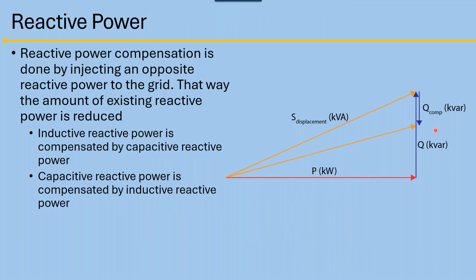Are there harmonics in kVAR? Does the capacitor or reactor have harmonics in it? The answer is no. What we got in the chat is yes, and that's wrong, because there are none. So that's why I call this displacement kVA, because right here there are no harmonics shown in this picture.